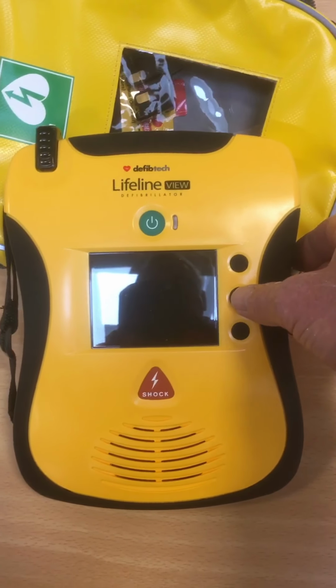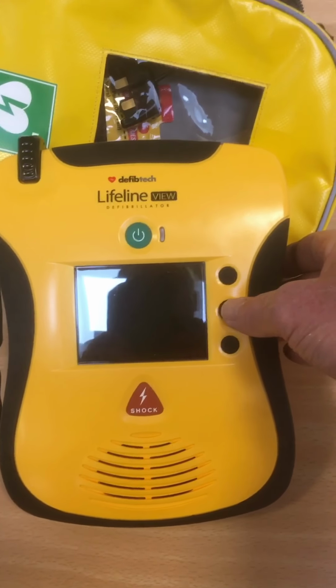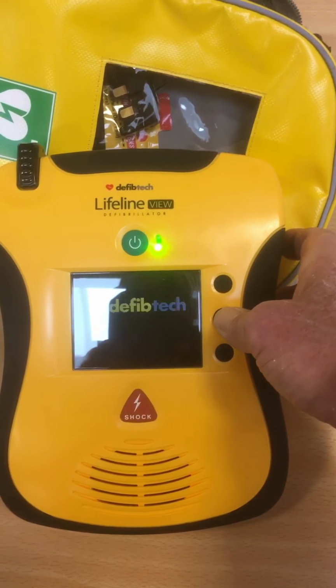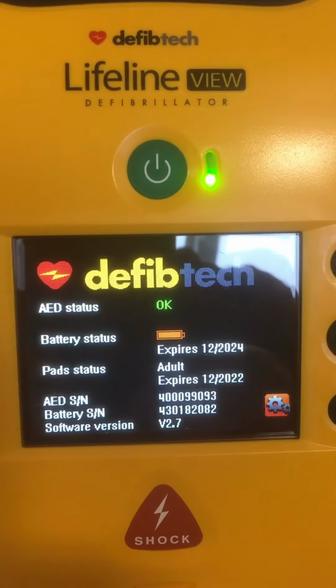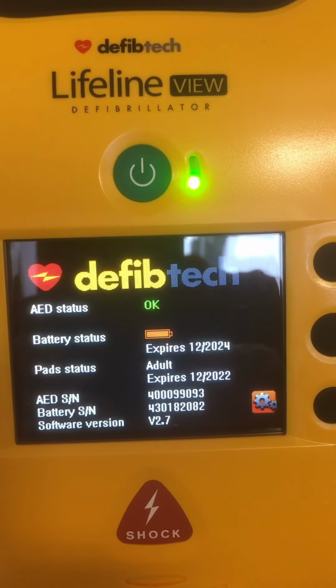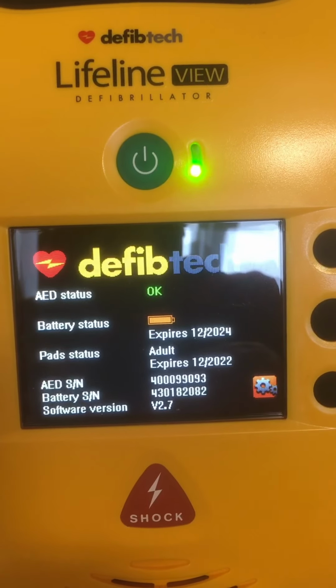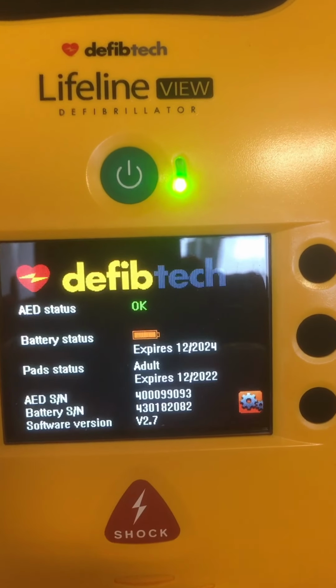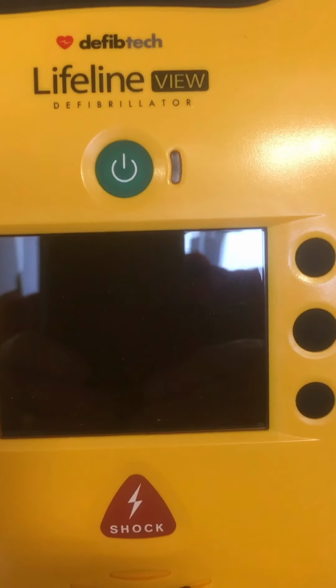The second test is once a month at least. You could do this as and when you open the cabinet - you simply press this button and hold it, and it will once again carry out its full test. In that test, it will tell you the battery status and the pad status, including when they expire. Our pads for use on patients expire in 2022.